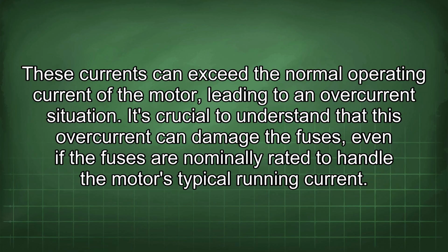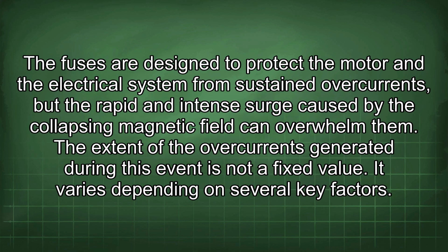It's crucial to understand that this overcurrent can damage the fuses, even if the fuses are nominally rated to handle the motor's typical running current. The fuses are designed to protect the motor and the electrical system from sustained overcurrents, but the rapid and intense surge caused by the collapsing magnetic field can overwhelm them. The extent of the overcurrents generated during this event is not a fixed value. It varies depending on several key factors.